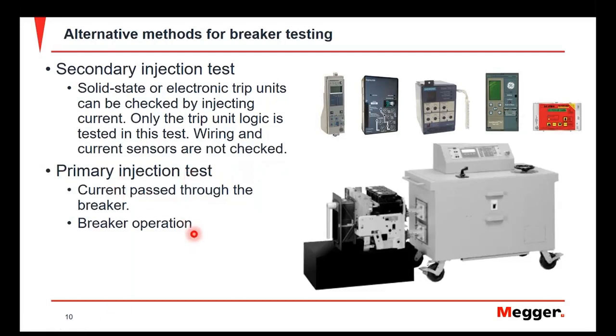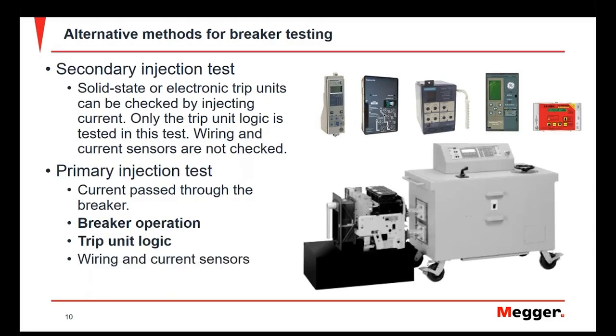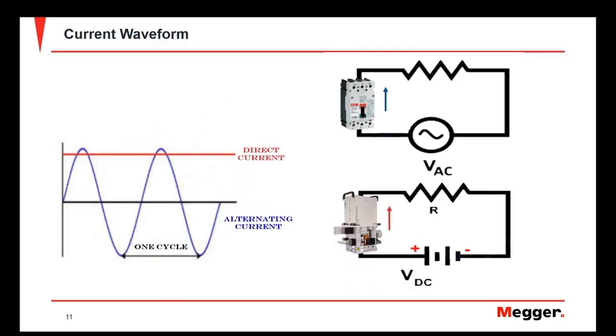Whenever we do a primary current injection test, we're testing for the breaker's overall operation, as well as checking the logic of the trip unit to make sure it's communicating properly with the other elements of the breaker, such as the current sensors and wiring associated with the trip unit. In other words, primary current injection is a complete system test to verify reliable operation whenever it needs to operate.